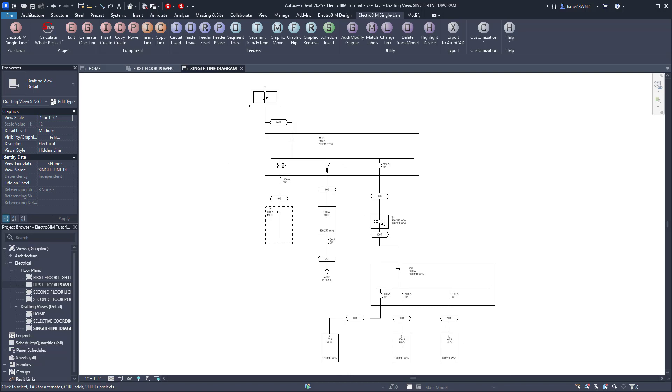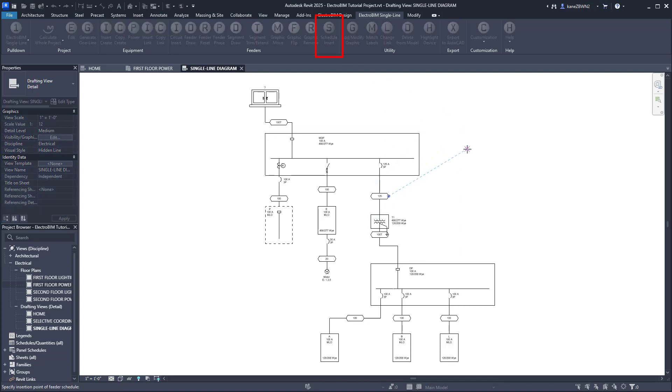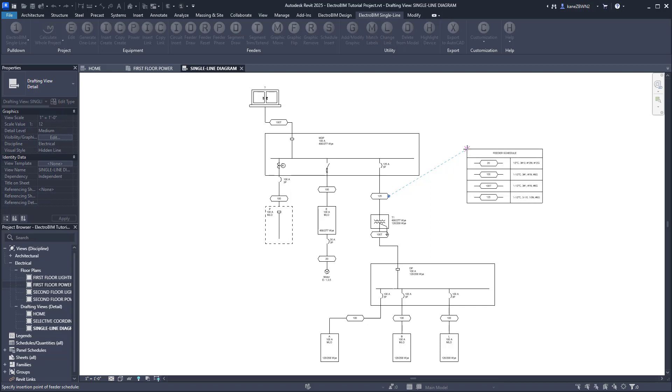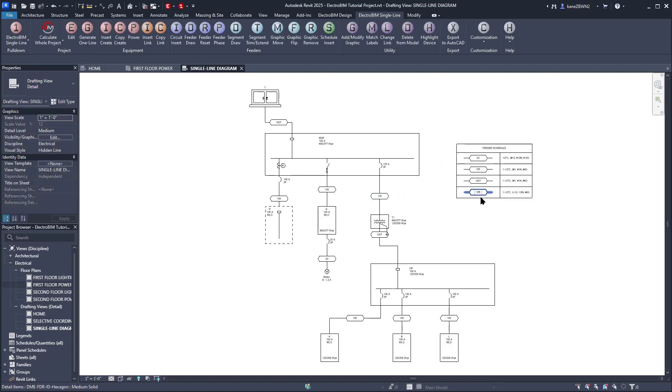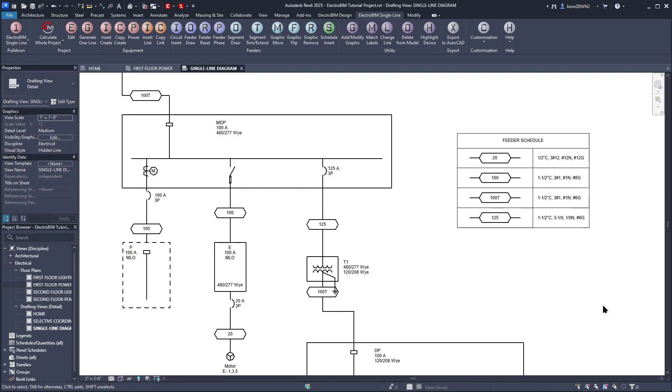We're just missing one thing here, and that's the Feeder Schedule to tell us what these IDs mean. To create the Feeder Schedule, run the Schedule Insert command. It will ask you to specify a location on the Drafting View. Wherever you pick, that's where the top left corner of the Schedule will go. We'll pick a spot over here, and there are the IDs currently displayed on the Single Line, as well as their corresponding callouts.